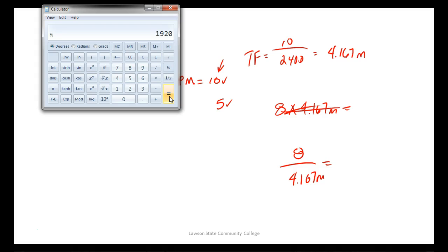So all I would have to do, if I had an A to D converter coming into my PLC, is figure out what binary number represented that, and then I could go directly to speed by doing a little math. So what would we get out at 5 volts? Well, I'd say 5, and then I would divide it by what we call our transfer function, and it says I should be running at exactly 1200 RPM, right?